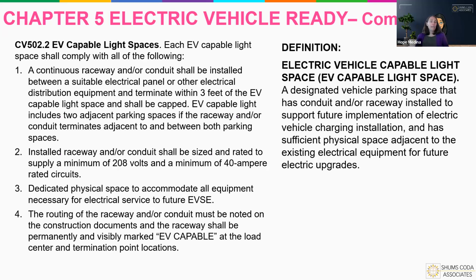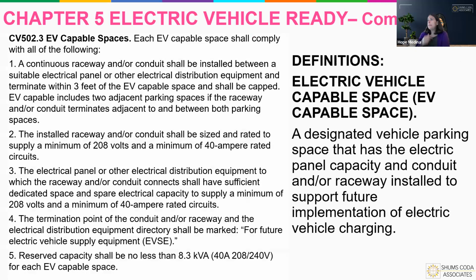Capable light is basically the least amount you can do. We just need to have that raceway or conduit, and the panel space. It's got to terminate within 3 feet of where the EV capable light space will be, and it needs to be capped. Any future equipment has to be capped off, and noted, and we have to make sure there's physical space to accommodate the equipment. We can't just designate the space and then have it piled up with everything else. There has to be a dedicated space reserved for future installation.